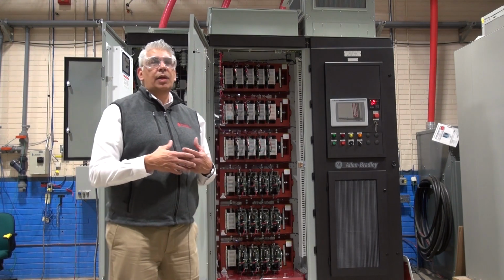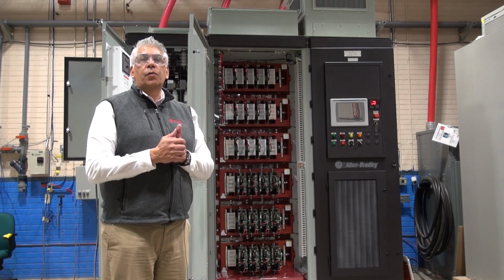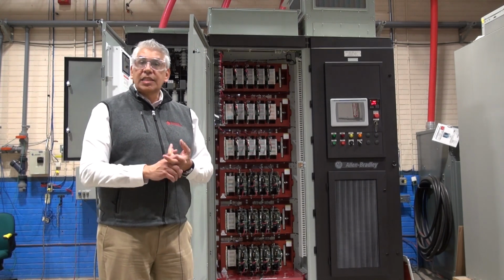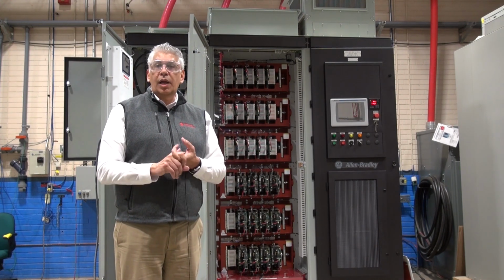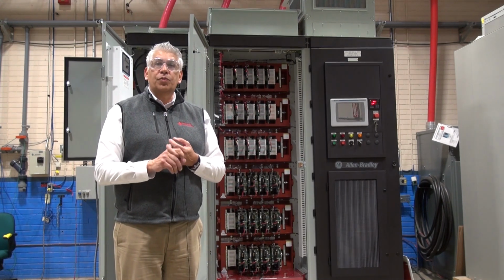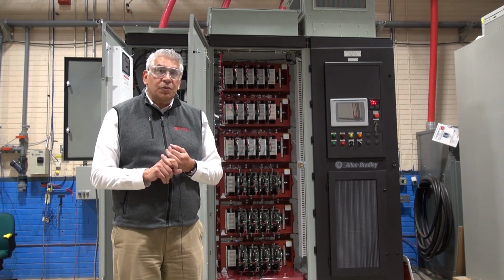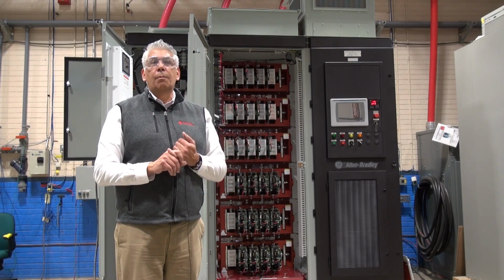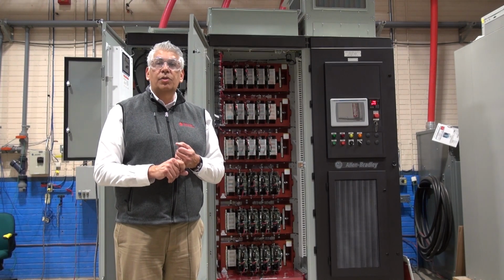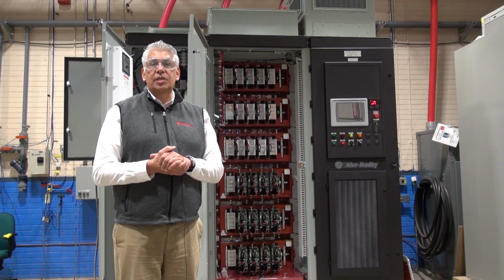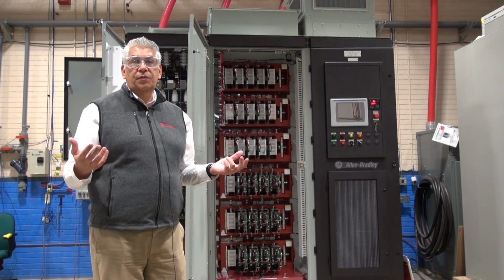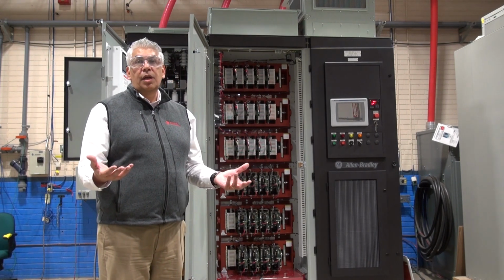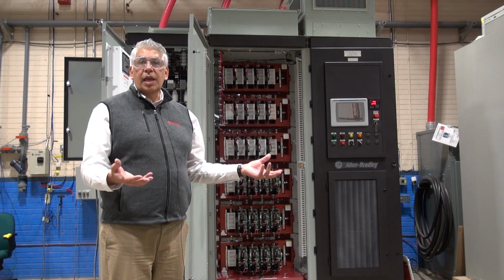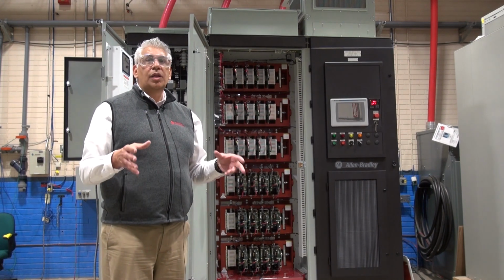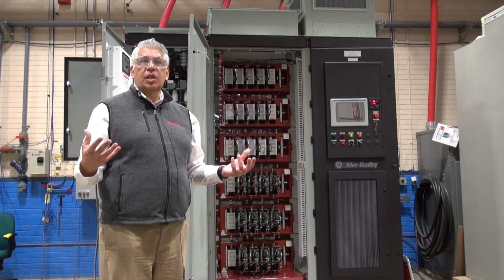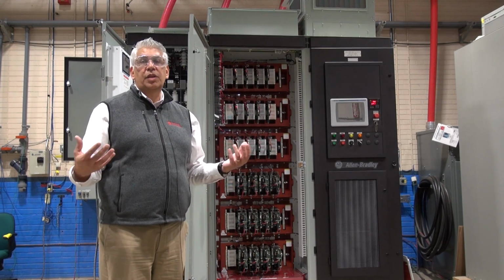And in addition to that, again keeping our product line as flexible as possible, we offer a variety of configurations as well. We have an 18-pulse transformer version that's really targeted to high-power constant torque applications. We have options for indoor and outdoor separate transformers, and an option for an integral transformer. Most of our product sales are around the direct-to-drive configuration that we're showing here in this example. The reason it's so popular is that it's a transformerless configuration, so the customer can bring in their cables from the utility, connect to the drive, 3 cables in, 3 cables out to the motor. So it's very small, very compact, and extremely high efficiency because it doesn't have the efficiency loss of an isolation transformer in front of it.